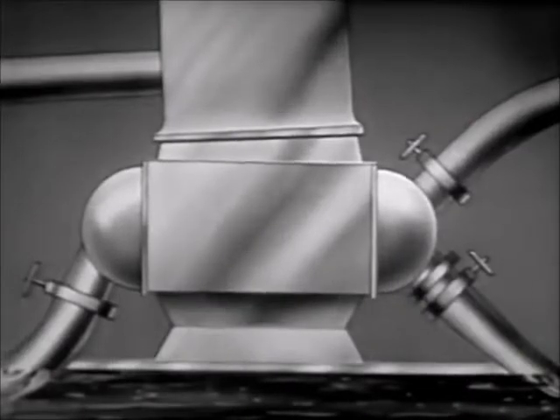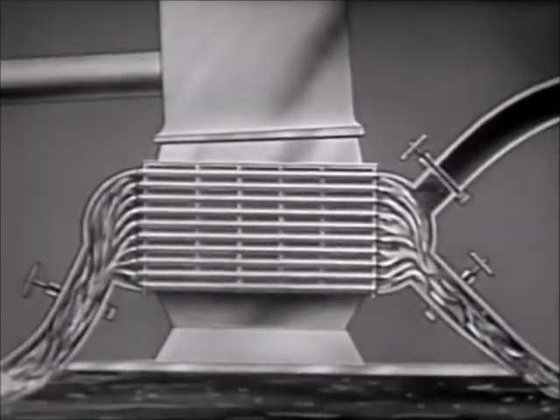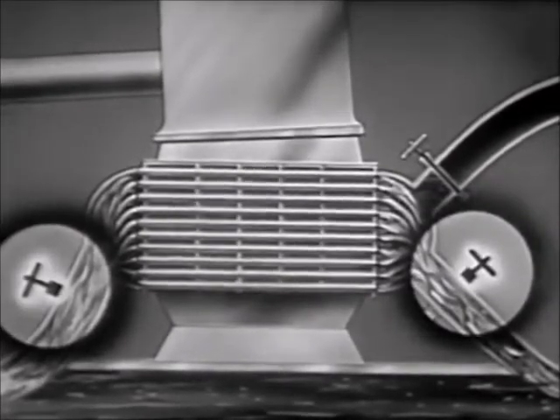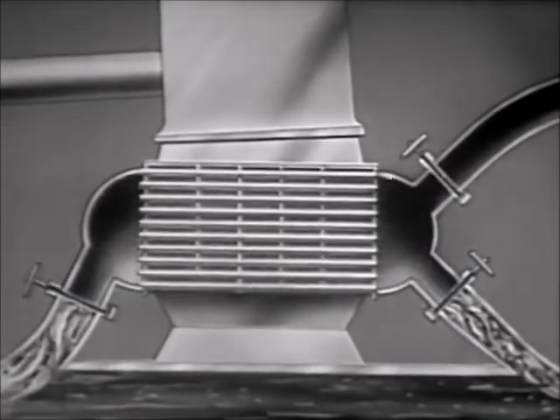The main condenser is located close to the ship's bottom, well below the waterline. Thus, open connections to the sea flood the water chests and tubes. However, there are 2 gate valves which can shut out the sea. With the gate valves closed, you can drain the condenser and open or remove the water chests for interior inspection and repair.